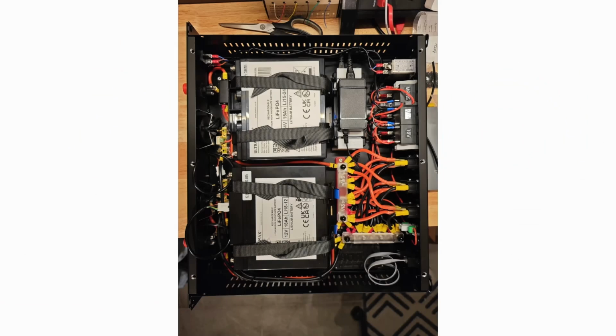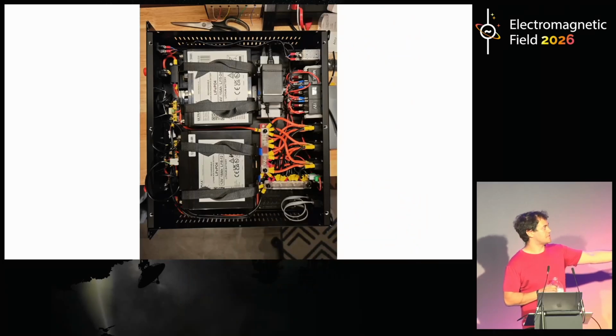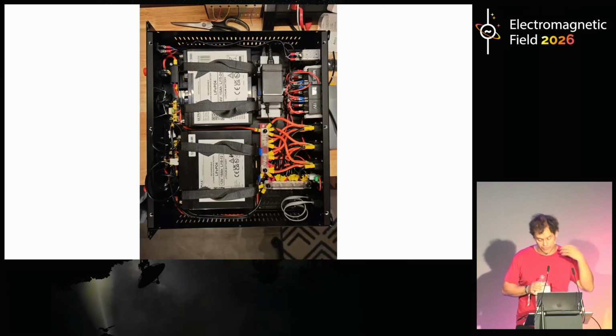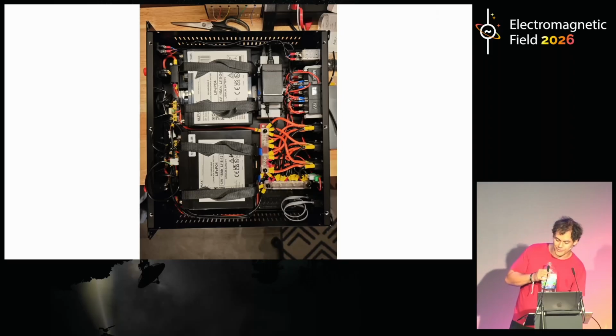The other thing we discovered was that if you get a power supply off the shelf, it's quite noisy. So they're quite good for most applications. They're not good for when you need the nanovolts coming out of an MRI scanner. So we had to build our own battery power supply that could run the gradient coils and run the RF system to make that work. And this was a fun safety challenge to make sure that we were not going to set fire to anything, which we haven't, which is good.